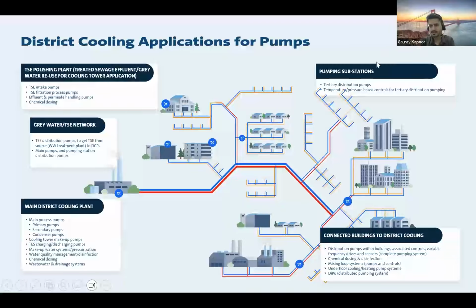Then there are pumping substations also. Sometimes that's more on the district heating side or a very large piping network of district cooling, where booster pumping substations come into the network. It means if the network is too large, where the secondary pumps cannot push the water till the end of the building, there will be a small pumping substation within the network to further pressurize the chilled water to reach the end of the building. And obviously in the buildings connected to district cooling, pumps are required for circulating the water within the building. There are different types of connections available. It can be directly connected or indirectly connected with the help of a heat exchanger system.